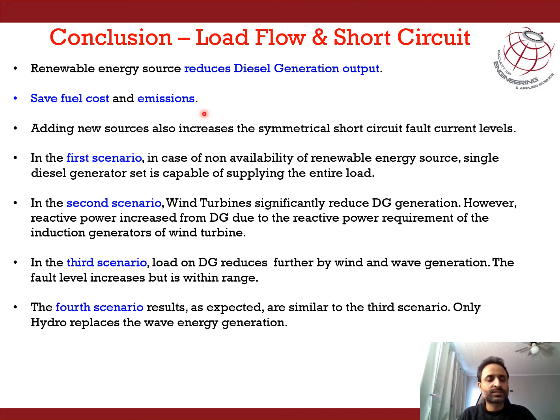However, connecting such renewable sources with the microgrid will result in an increase in the short circuit fault levels. As a result, there is a requirement to carry out load flow and short circuit studies. In the first scenario, we indicated that if none of the renewable energy sources are available, then the diesel generator is capable of supplying the entire load.